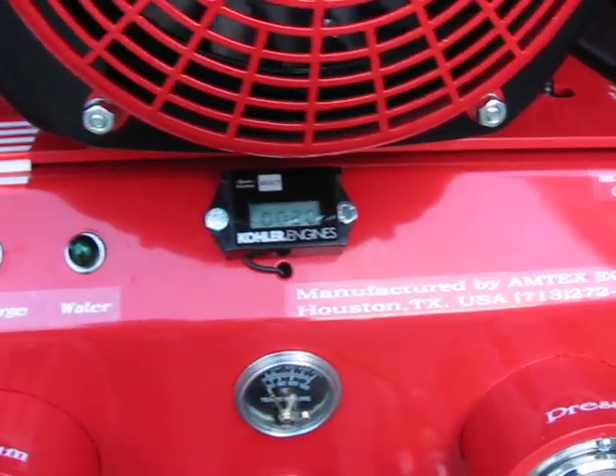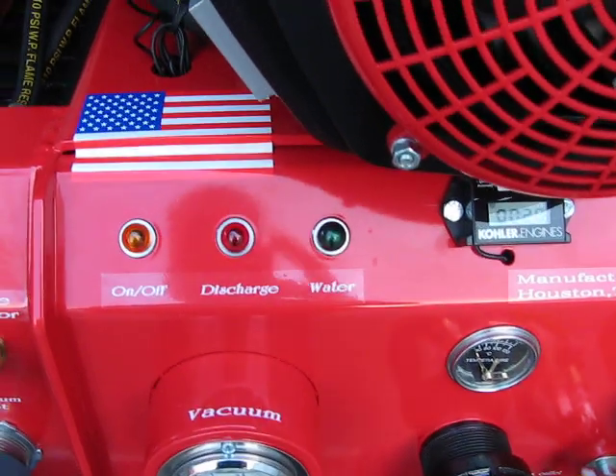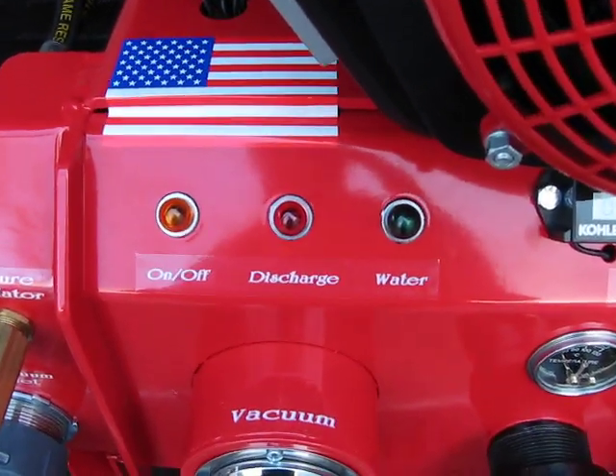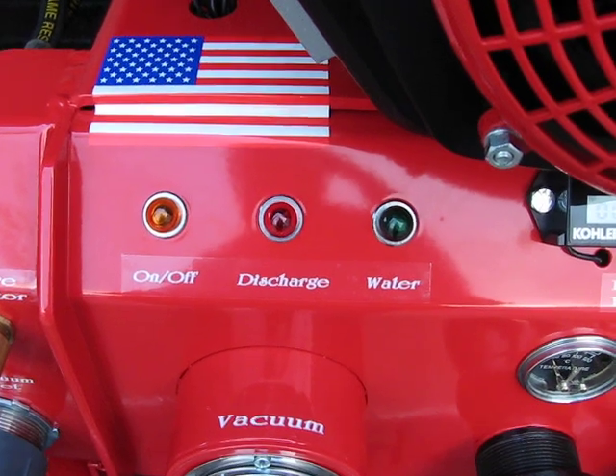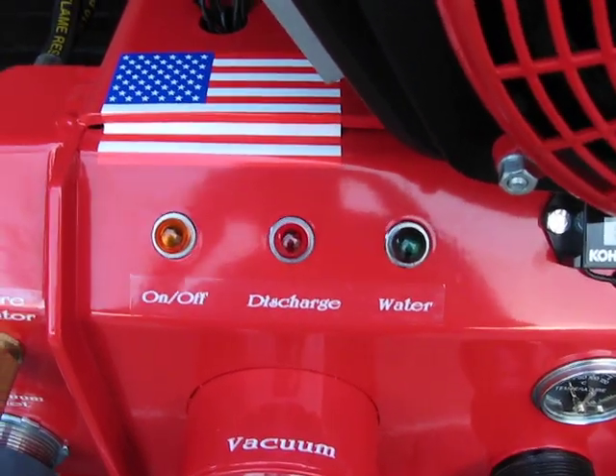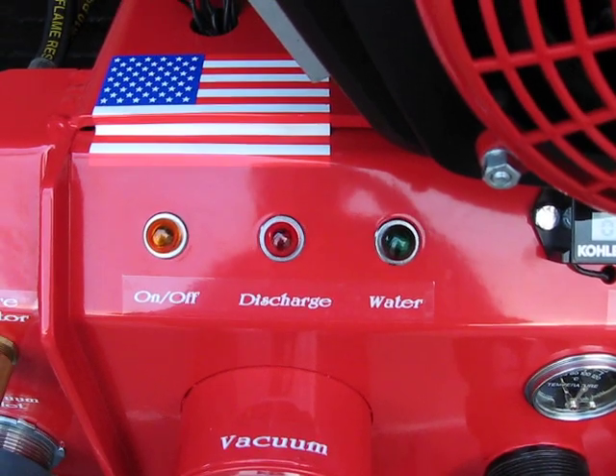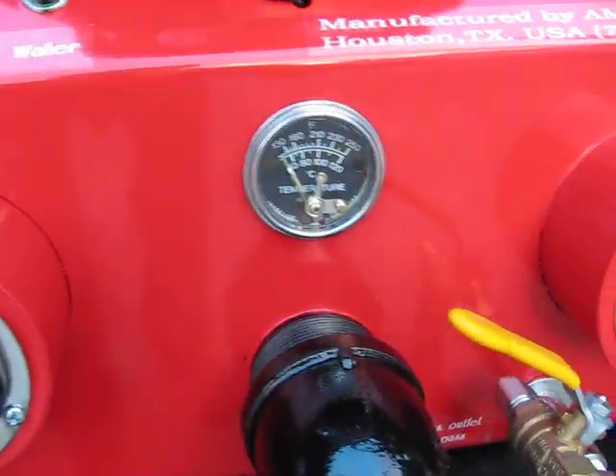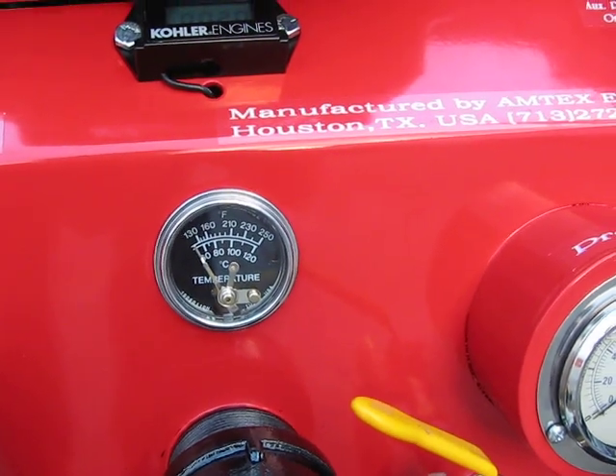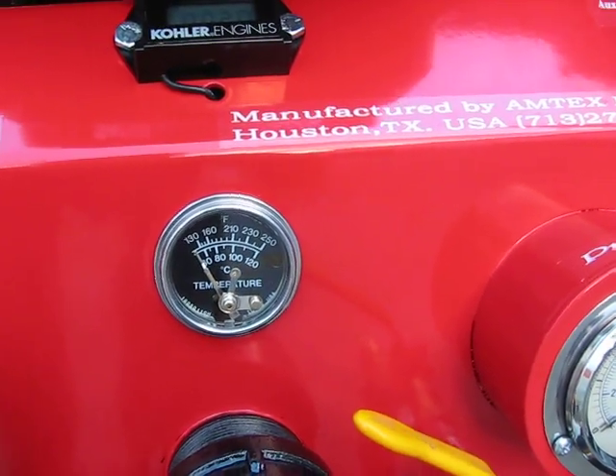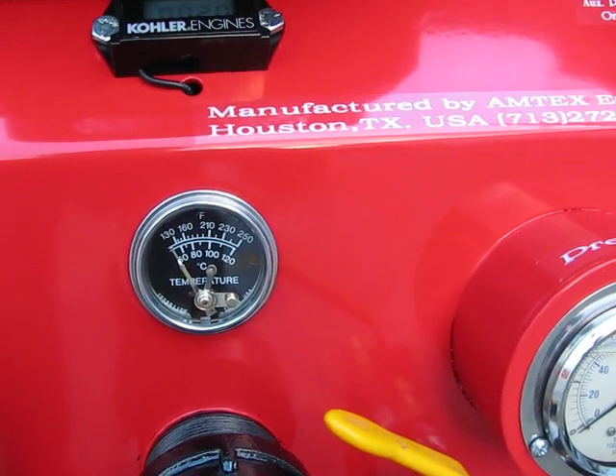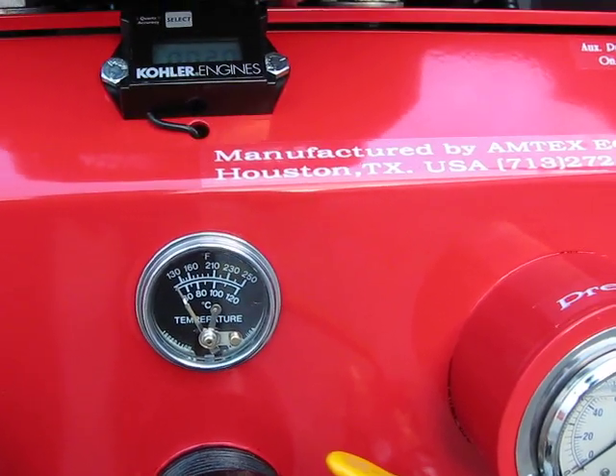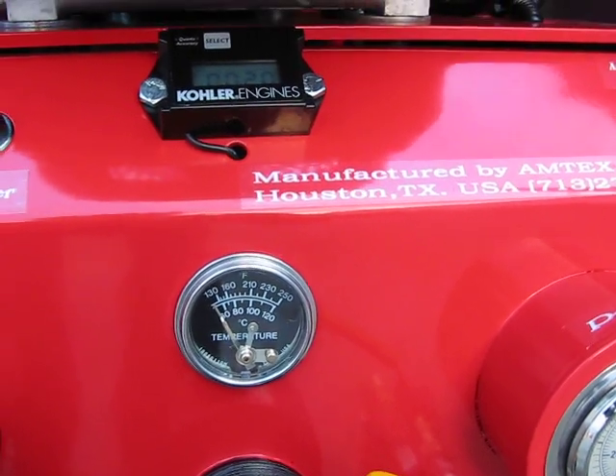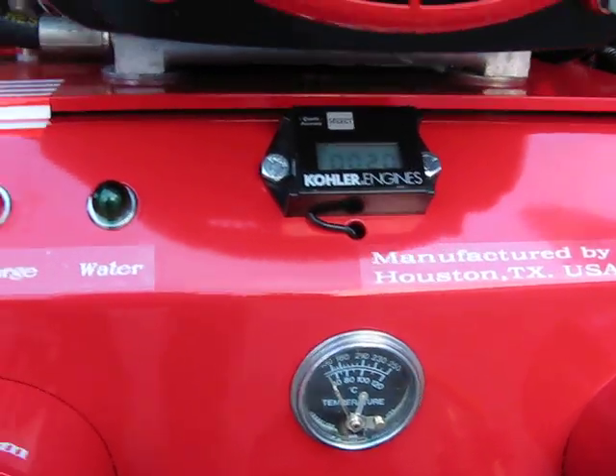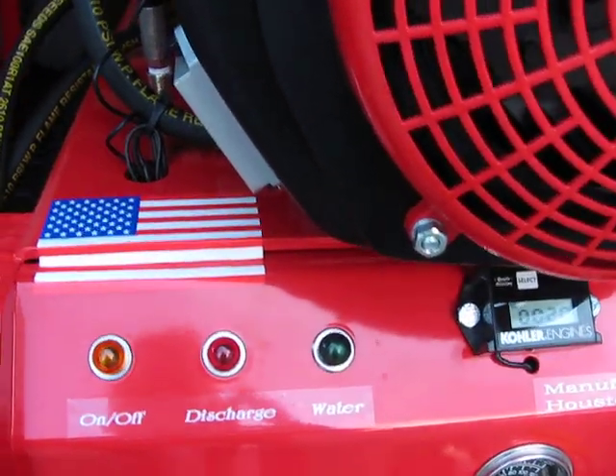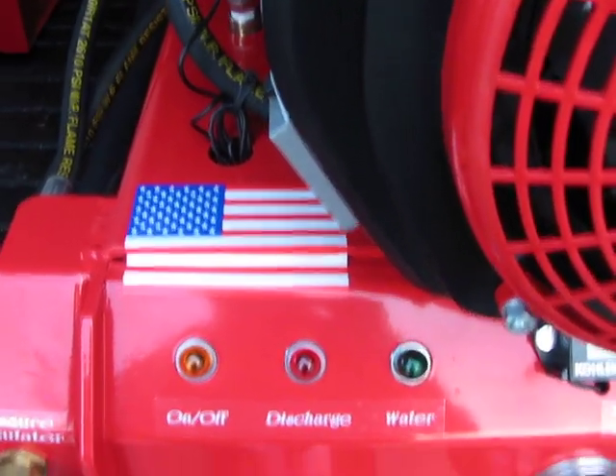So, to the left of it, you do have your indicator lights. The green light is used to show you that you have a good flow of water coming in. The center red light is called discharge, which what we mean in this case, discharging extra heat. So if we have the temperature set at 220, once the temperature rises and reaches that point, if you're not using the water, and because the heat exchangers are constantly producing hot water, at that point the machine automatically pumps some of the hot water out of the heat exchangers into the recovery tank. In that case, your red light comes on and shows you that that operation is being done.